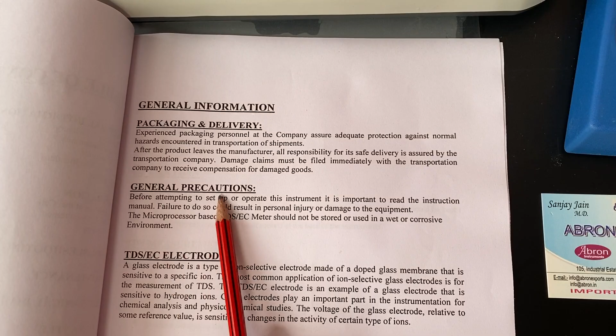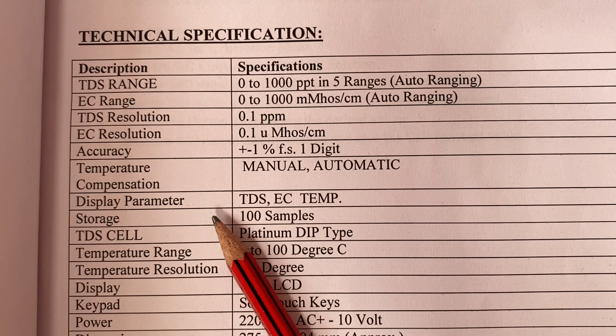It will give you automatic ranging. The EC range is also up to 1000 millimho per cm, auto ranging. TDS resolution is 0.1 and EC resolution is 0.1 microsiemens. Temperature compensation is manual or automatic. You can remove the automatic temperature compensation, and it will work manually also.